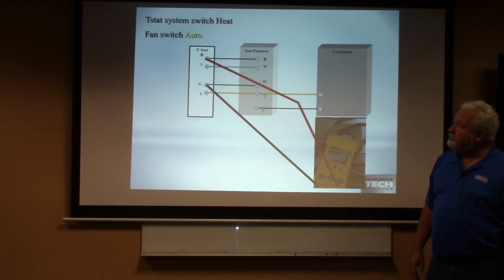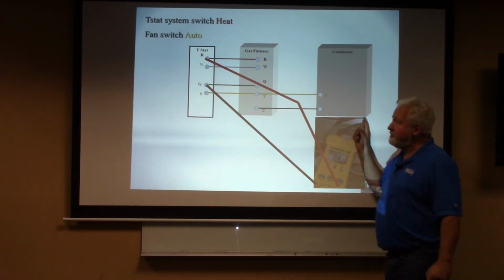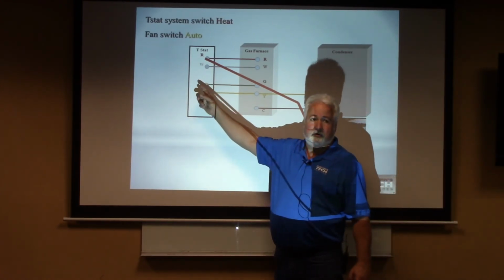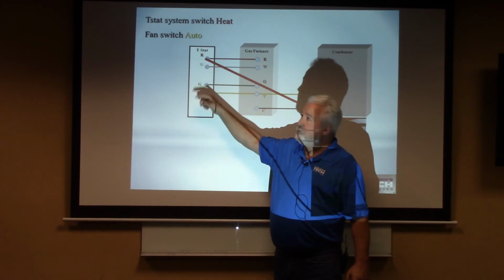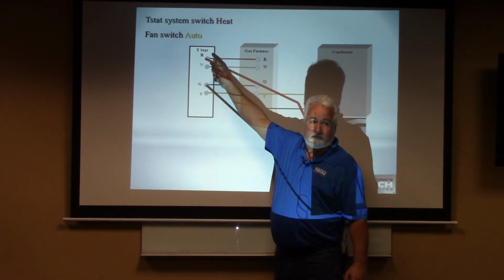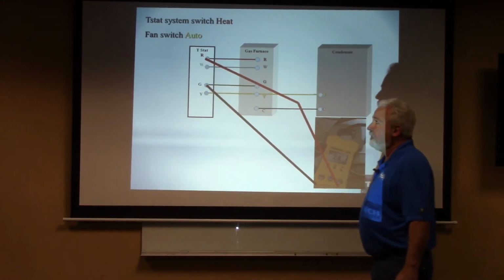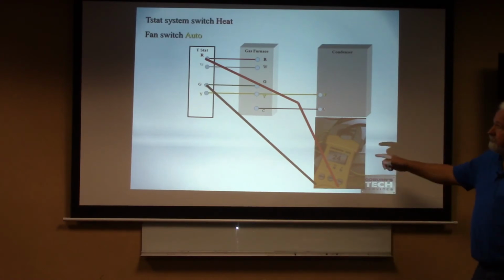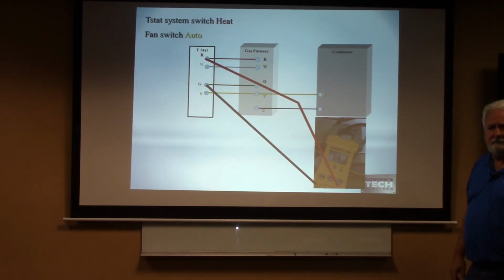All right. Let's do R and G on that heating mode. What am I going to see? 24. Absolutely, I will. Will I see the common side coming back to this side of the G? Will I see the R potential? Absolutely, I will. Sure. So 24 volts there. Doesn't mean that the fan's running, does it? Nope.